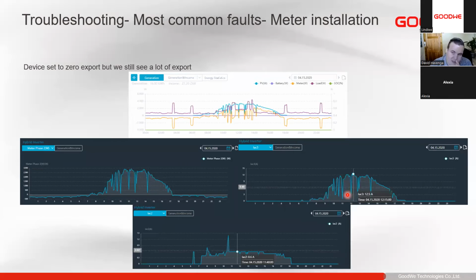So that's why it's very important to make sure that the phases on the smart meter match the phases on the inverter, especially if you are using the unbalanced output. If you're not using the unbalanced output, you wouldn't have this problem. But for the countries with 0 export, unbalanced output is the best way to get the most production. So it's always advisable to make sure that your voltage sense and your CTs match exactly the inverter's input.